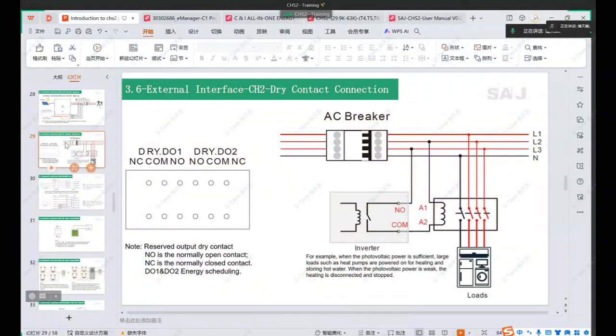And this is our dry contact connection. And as you can see, this NO is the normally open contact, and the NC is the normally closed contact. And the DO1, DO2 is for energy scheduling. As you can see in this example, when the PV power is sufficient, large loads such as heat pumps can go through our dry contact connection for heating and storing hot water. But when the PV power is weak, the dry contact connection will be switched off, and it will be disconnected and stopped. This is the highlight.